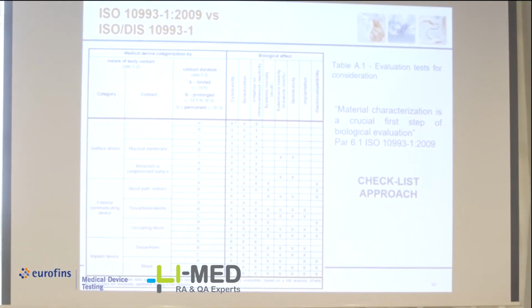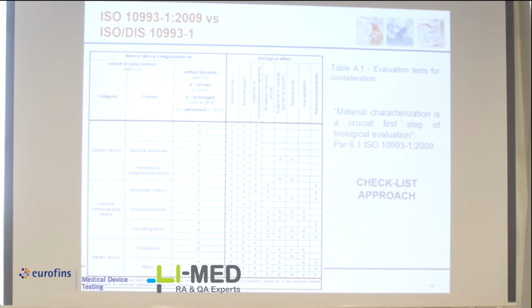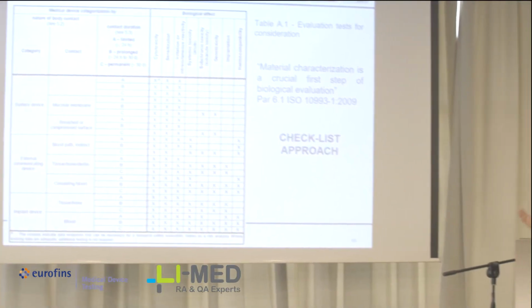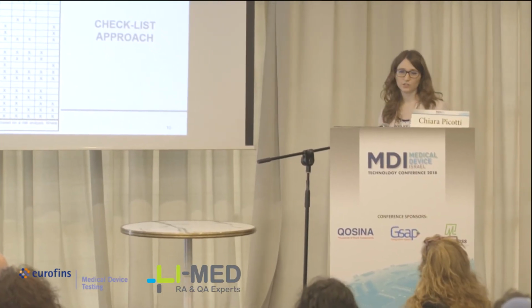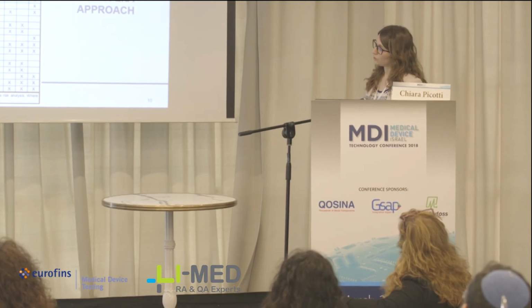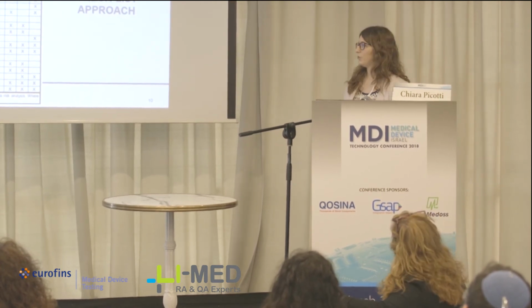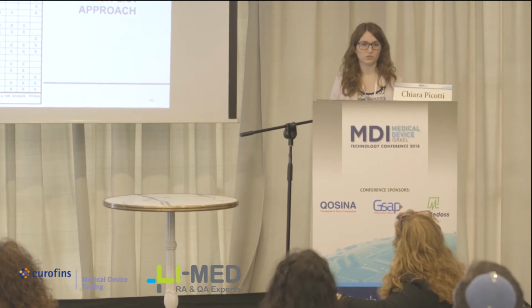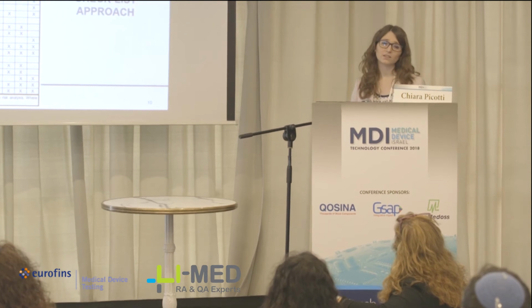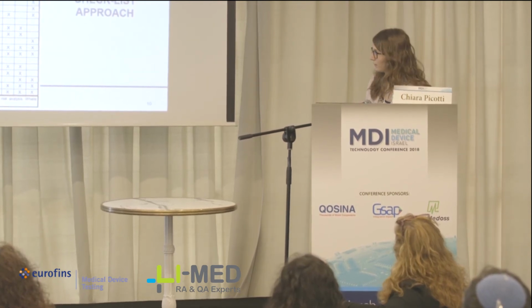So now the approach is changing a lot. This checklist approach is no more suitable because it doesn't consider a lot of important issues related to the medical devices. And for sure, it doesn't allow a full understanding of our device. So basically, these biological effects are considered a sort of suggestion, and the table should be considered as a framework through which we are able to identify the biological effect considered relevant and that we should assess. But it's not necessary to perform all the tests for all the endpoints, because in this case, we can lead to unnecessary testing. So this is the reason why now the table is changing a lot.